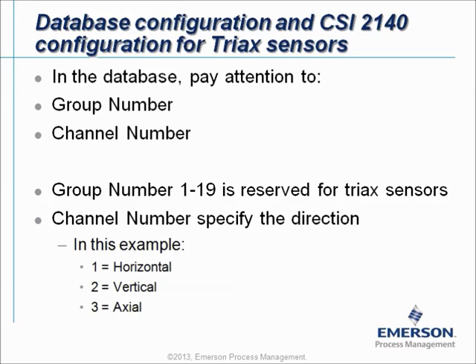If you configure the database to work with the Triax sensor, you have to pay attention to two special things. All the measurement points that are in the same measurement plane have to receive the same group number. The channel number will specify the direction of measurement. Group numbers 1 through 19 are reserved for Triax sensors. The channel numbers specify the direction — in this example, 1 is horizontal, 2 is vertical, and 3 is axial.